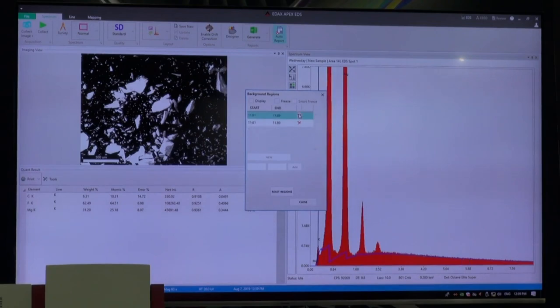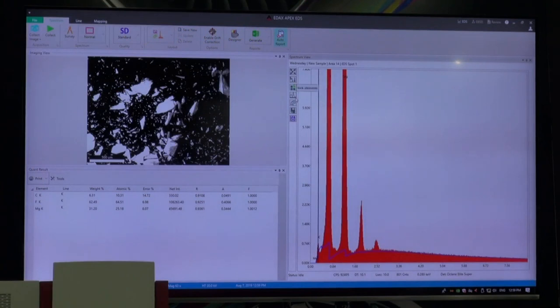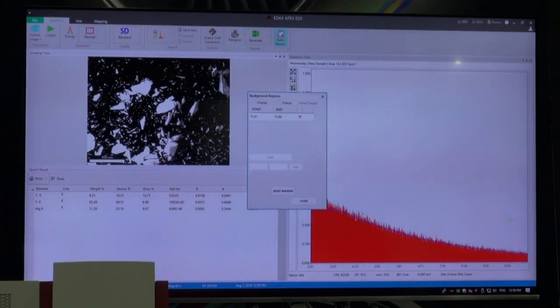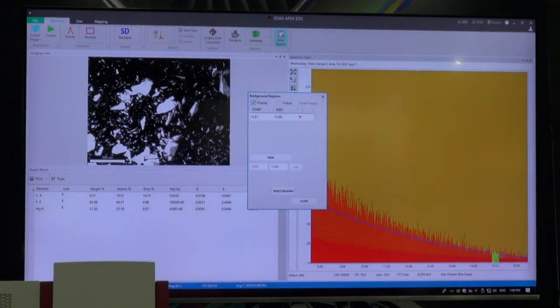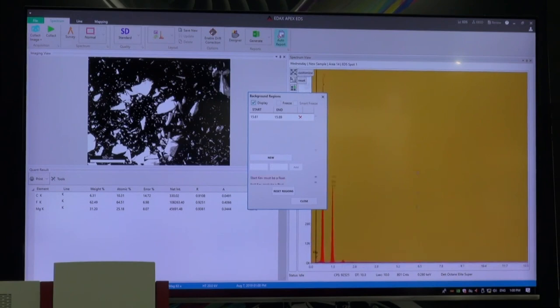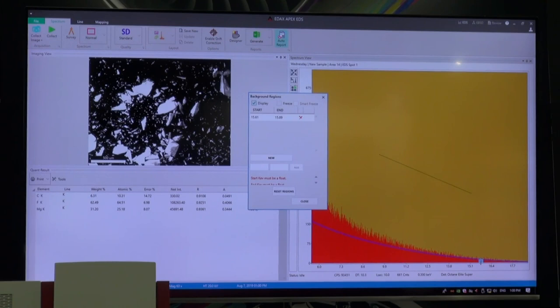The model is based on a basic fit — it's essentially a series expansion of Kramers' law. We can add more fit regions to modify and make the curve look better. But the essence is: if my sample is meeting the requirements of the quantification model, I should be able to get a good background fit with a single background region — just give it an anchor point and it calculates the Bremsstrahlung all the way down to the low energy range.